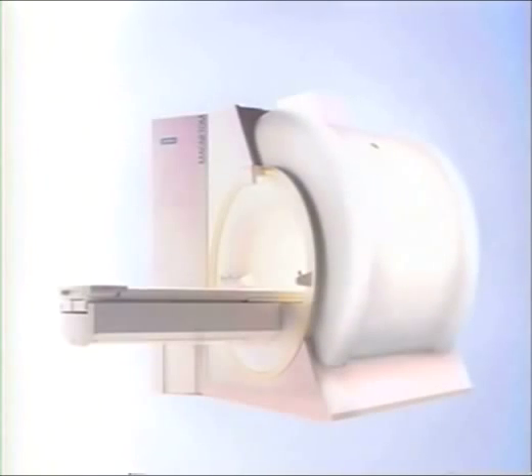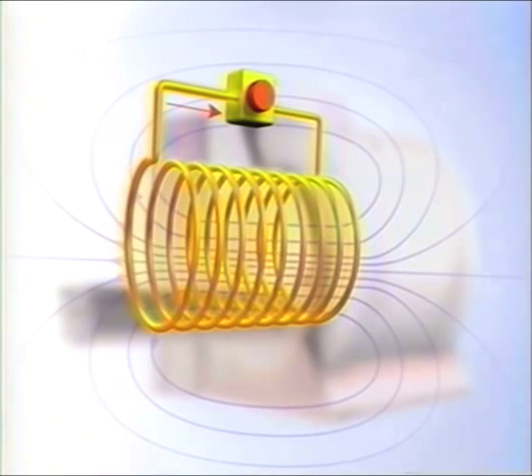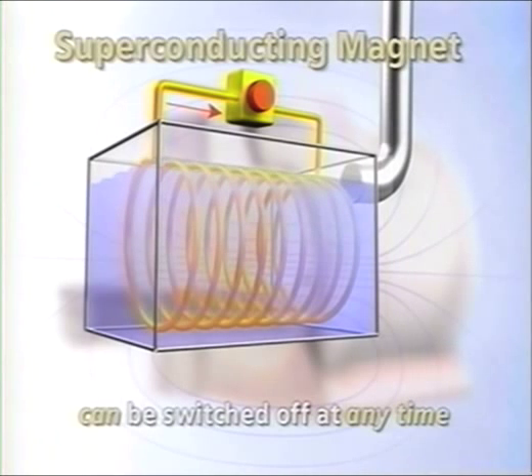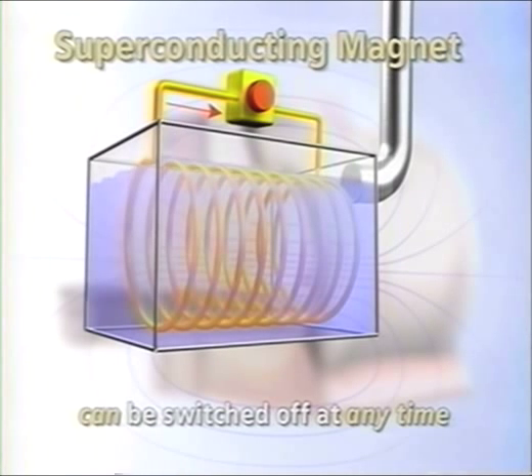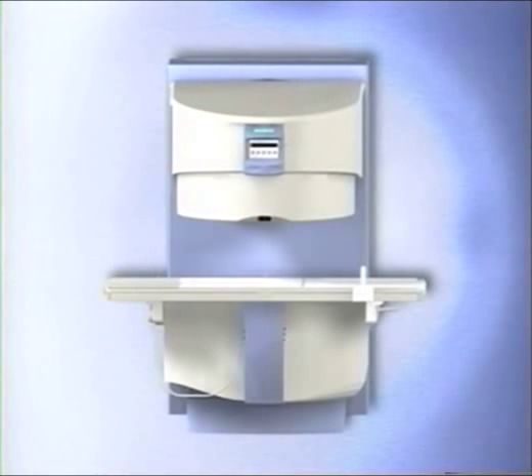Superconducting magnets are used to generate higher magnetic field strengths. In this case, the wire coils through which the current flows are cooled by liquid helium to 4 Kelvin above absolute zero, which is minus 269 degrees Celsius. The current is provided by a power supply unit during installation. But once superconducting, it can flow without an external power supply for several decades. Once cold, the current flows continuously through the circuit and generates the static magnetic field. In case of an emergency, a superconductive electromagnet can be switched off at any time.